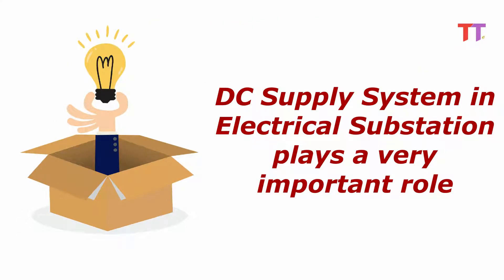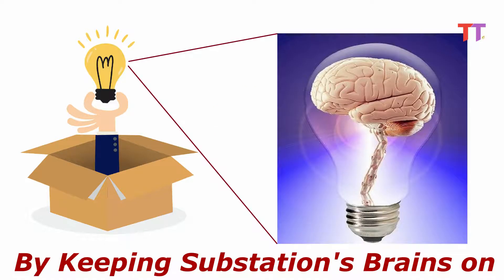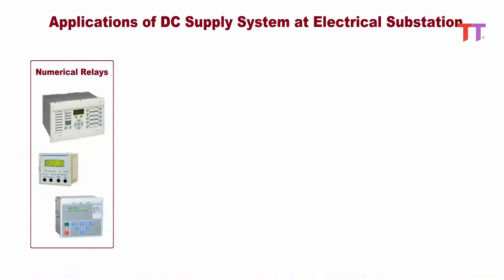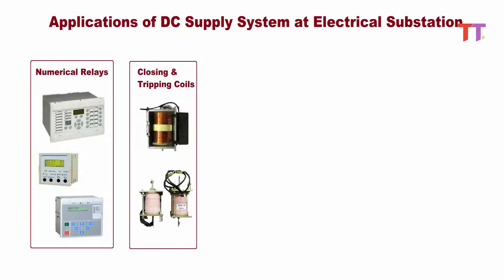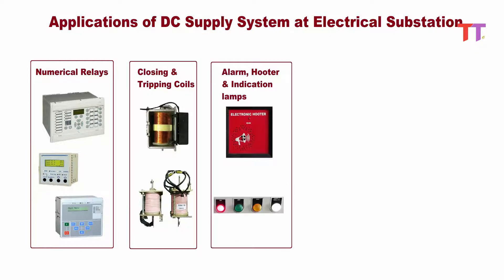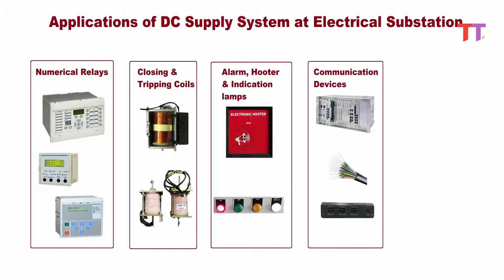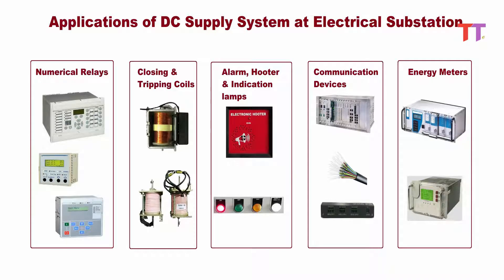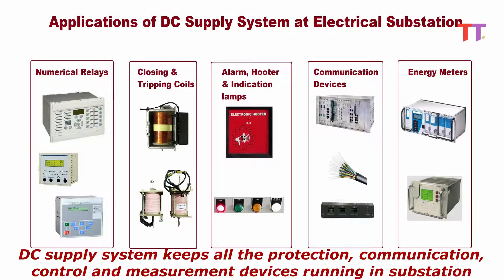DC supply system in electrical substation plays a very important role by keeping the substation's brains on. All modern numerical protection relays, closing and tripping coils, alarms, hooters, indications, and communication devices are powered by DC. Also, some energy meters are powered by DC. Hence, DC supply system keeps all the protection, communication, control, and measurement devices running in the substation.